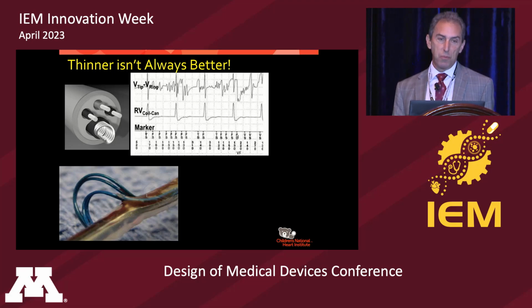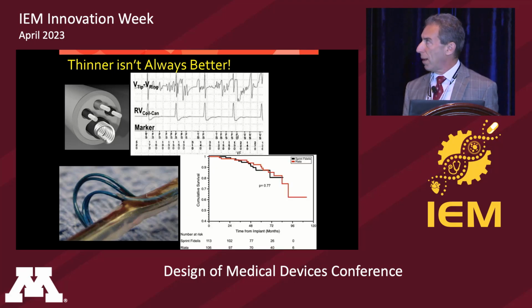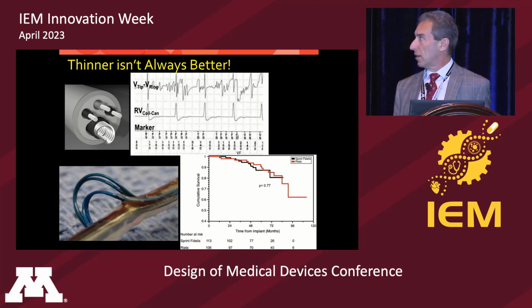And so there's more things that can break in a complicated lead. And here's two examples of problems with thin leads without naming names. Well, I guess they are named there. So this is a thin lead that had problems with the insulation between the conductors, causing electrical noise. And sometimes, for those who don't read these channels, this is marking fibrillation sense. And so the device thinks that the patient is in ventricular fibrillation and will try to deliver a shock.